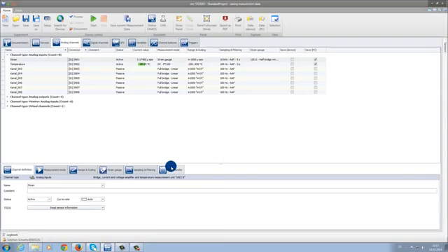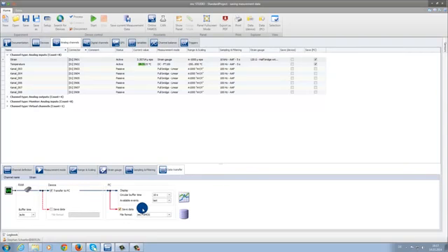In IMC Studio 5.0, you also have the possibility to save the current measurement data. As the button reads, this function only saves the current measurement data and not the entire measurement itself. For example, if you are using triggering functions, these events wouldn't be saved. The only thing that is saved with this function are the current measurement values themselves that are in the RAM. This is related to the circular buffer time settings, which are back in the Setup plugin and are independent from checking the box Save Measurement Data.